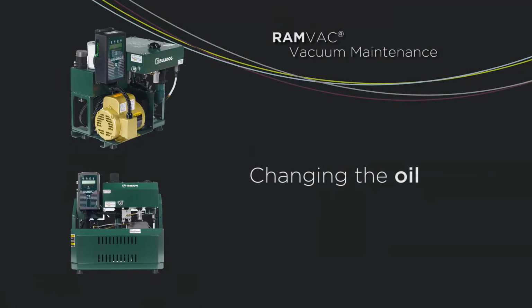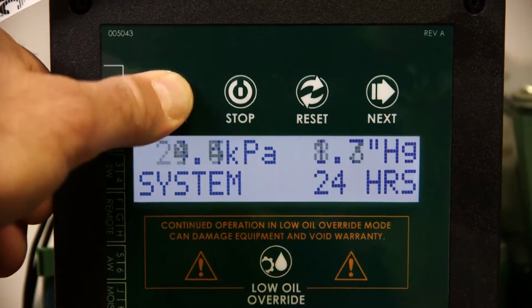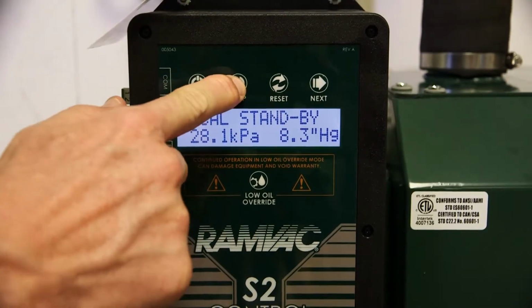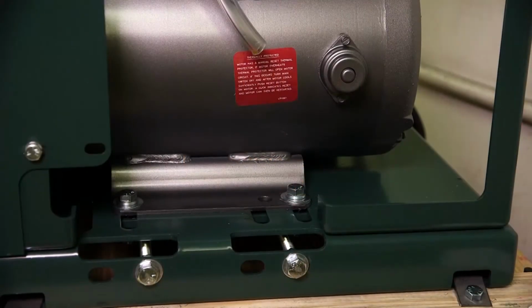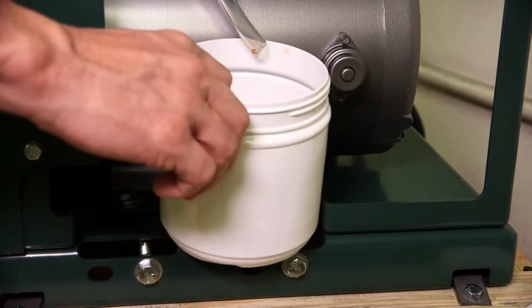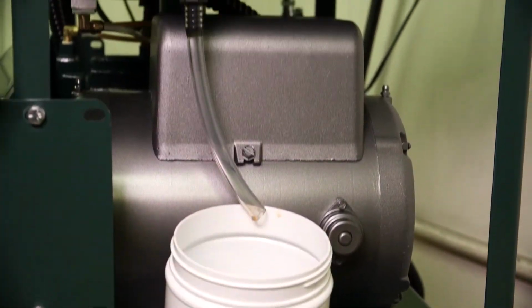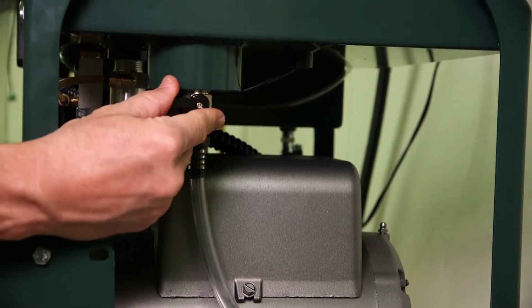Changing the oil. Start by operating the vacuum pump until the oil reserve is warm to the touch. Next, turn the vacuum pump off. Third, insert a container large enough to hold the used oil under the oil drain tube. The fourth step is to carefully open the oil reservoir drain valve and drain the oil.